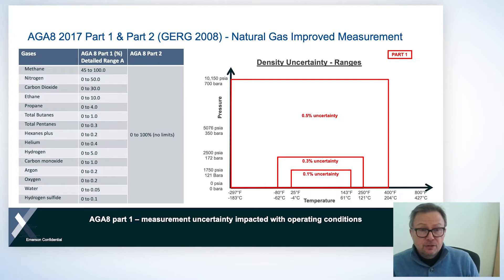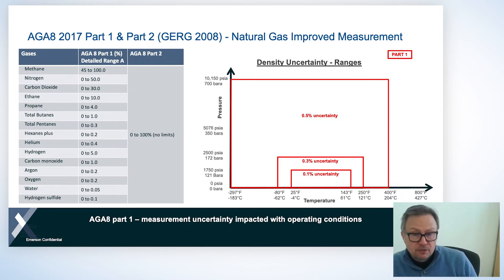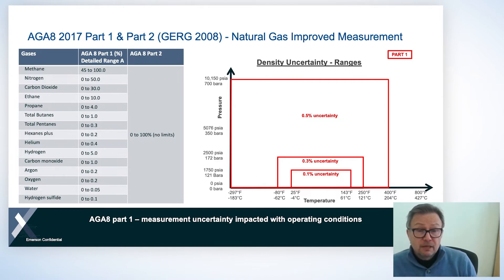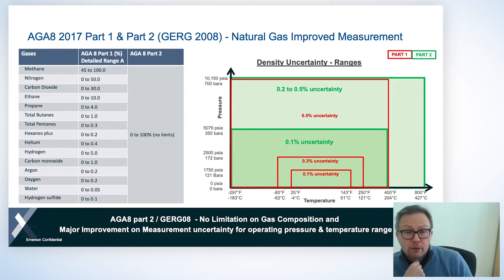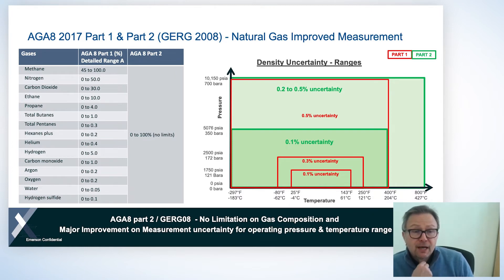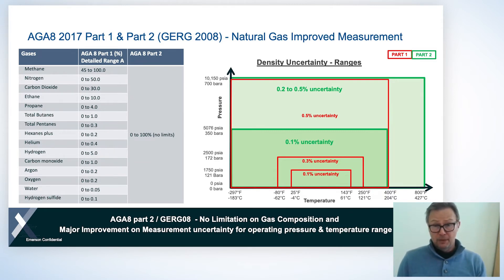Looking at part one on the right hand side, you can see the density measurement uncertainty. There's a small box in red at the bottom showing 0.1% uncertainty — that covers a temperature range of 25 to 143 Fahrenheit and up to 1700 PSI. Once you get outside that operating envelope, the measurement uncertainty increases to 0.3 or 0.5%. If we bring in AGA8 part two in the green box, the darker green box shows the wider applicability of part two, wider pressure and temperature range, and that still gives us 0.1% measurement uncertainty for density.